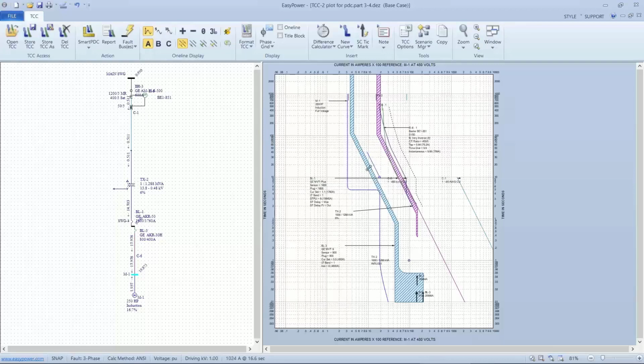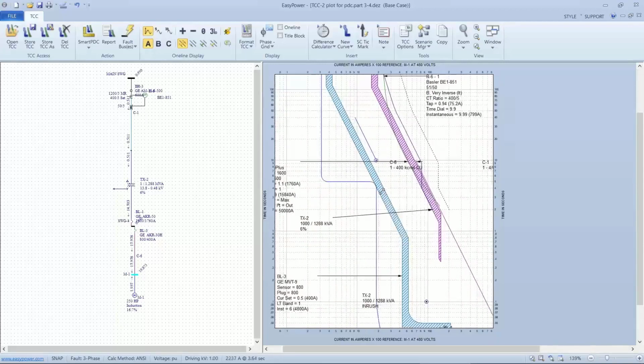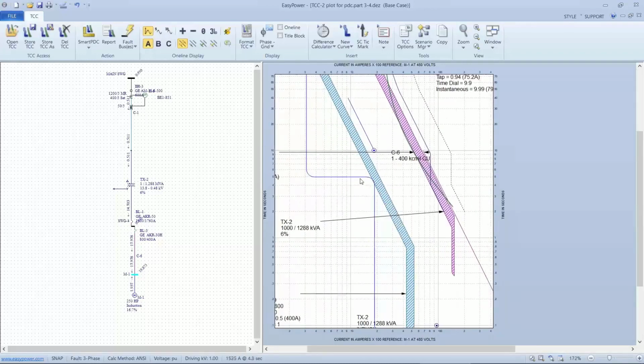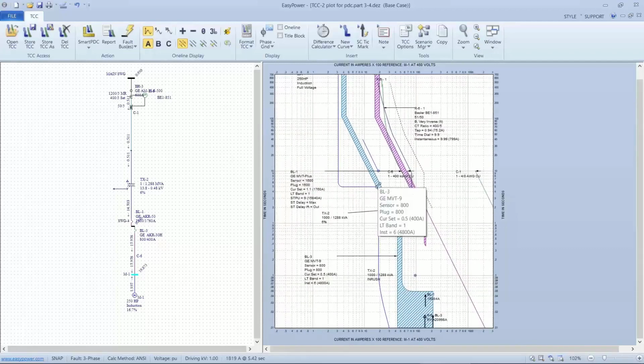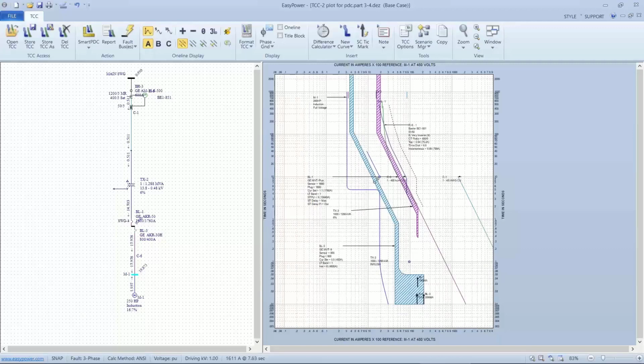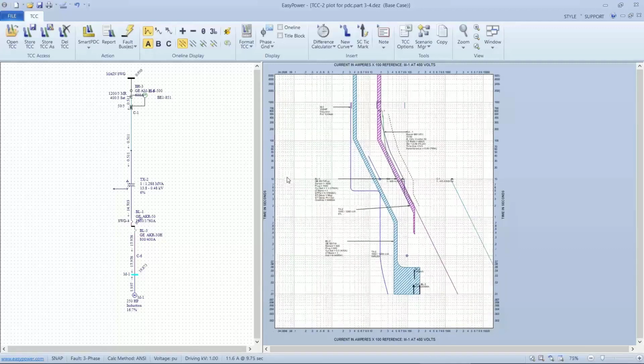The motor coordinated with the motor. Okay, so the motor is the violet curve, and the first upstream breaker is BL3, and it's close to being coordinated. I have some risk of an overlap here. Some of that is due to the locked rotor current that we've set up. Some of it is due to the granularity of the breaker curve itself. So let's say we've gotten beyond this point. The next thing I want to show or prove is once I've got this coordinated with the largest downstream motor, in this case 250 horsepower, will it coordinate with all the rest of the devices on the feeder, on the main bus?